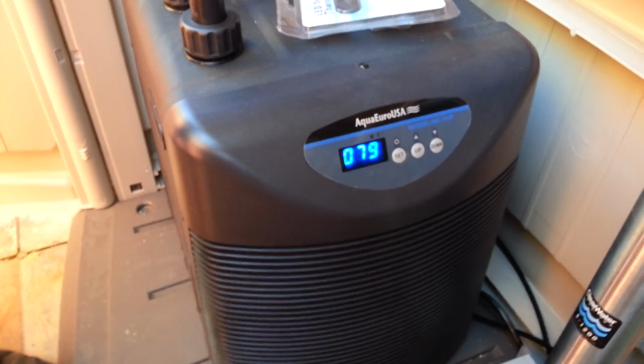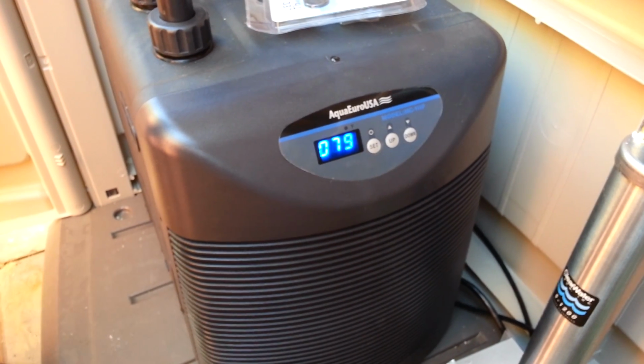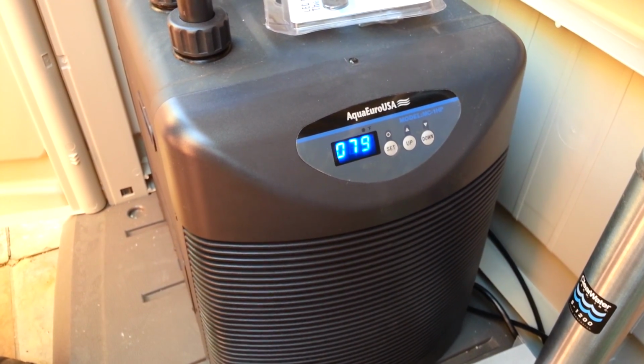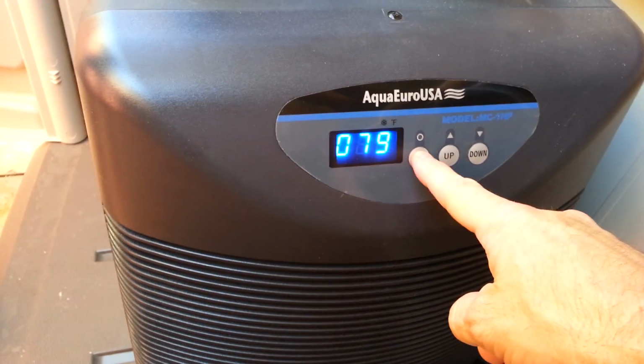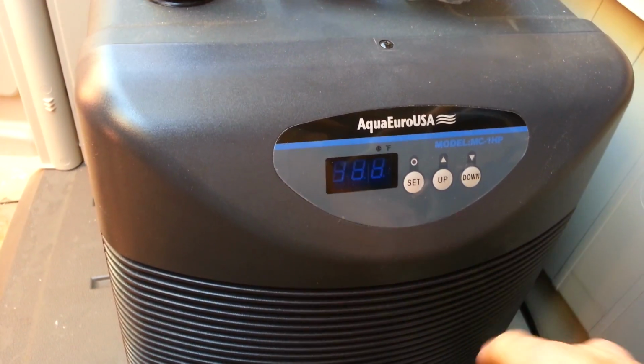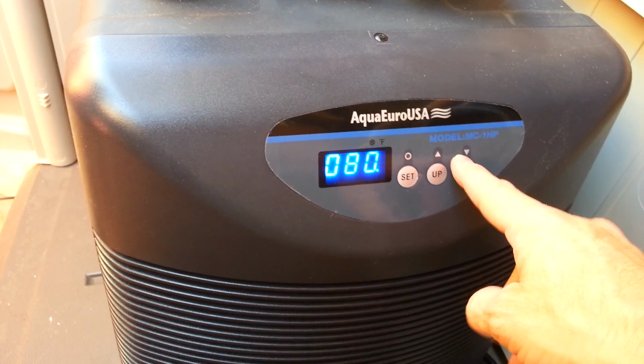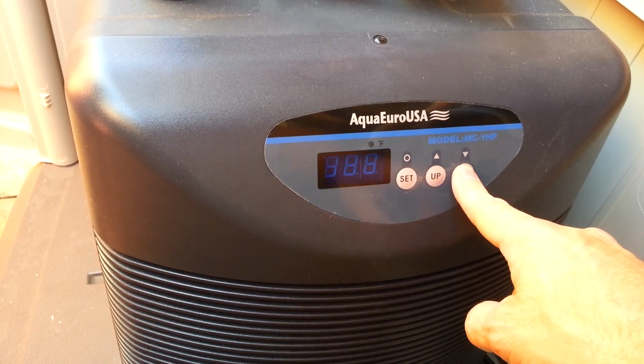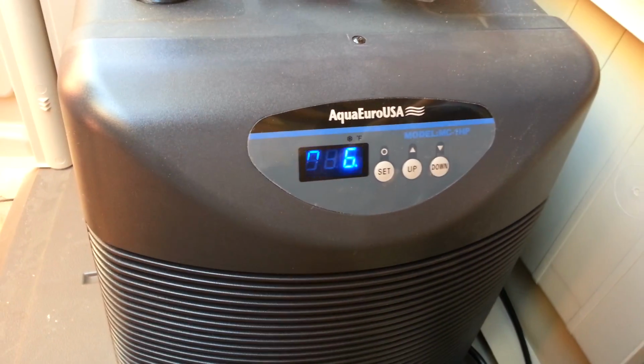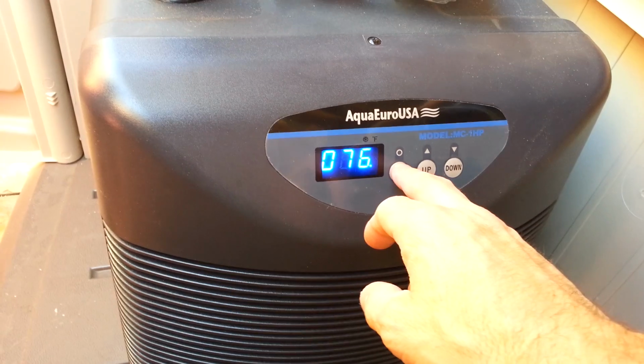That's here, 79 degrees. Right now the set point's at 82, so the chiller doesn't come on. It's just reading the temperature, but it's not activating. So what I'm going to do, we're going to change the set point from 82 back down to, say, 76. That way it's 3 degrees lower than the actual temperature.